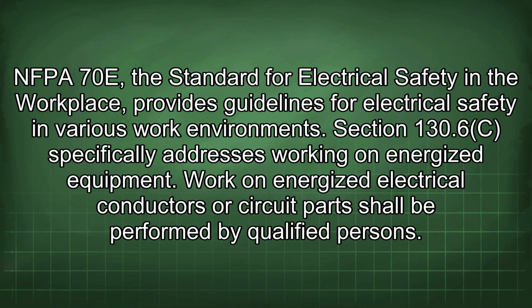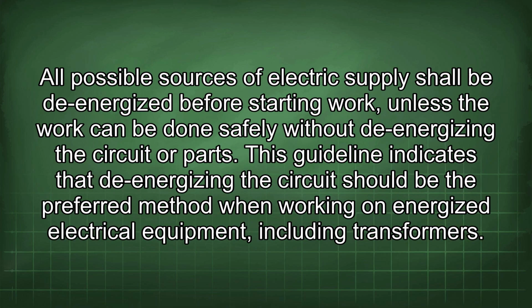Section 130.6c specifically addresses working on energized equipment. Work on energized electrical conductors or circuit parts shall be performed by qualified persons. All possible sources of electric supply shall be de-energized before starting work, unless the work can be done safely without de-energizing the circuit or part. This guideline indicates that de-energizing the circuit should be the preferred method when working on energized electrical equipment, including transformers.